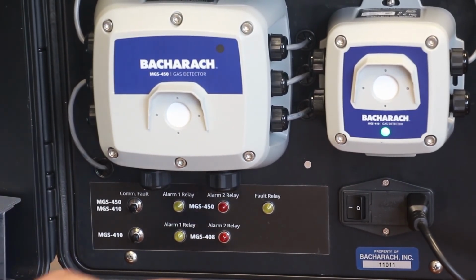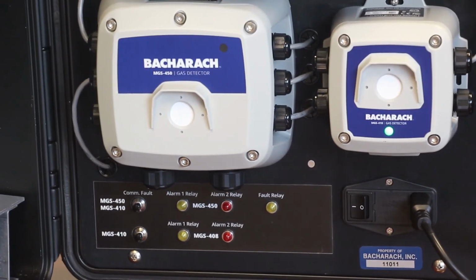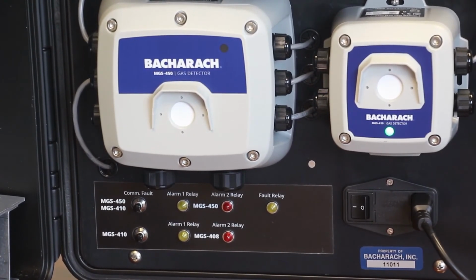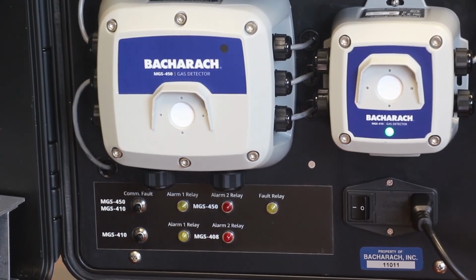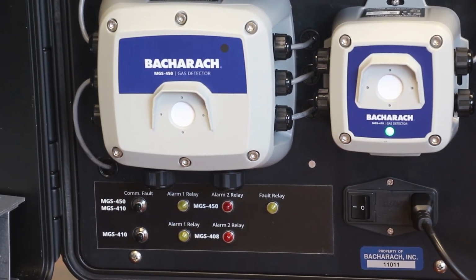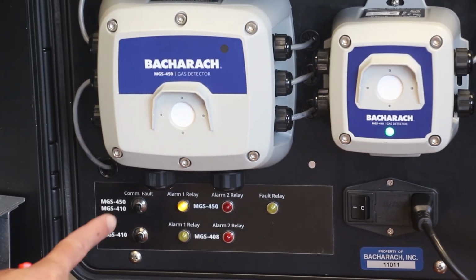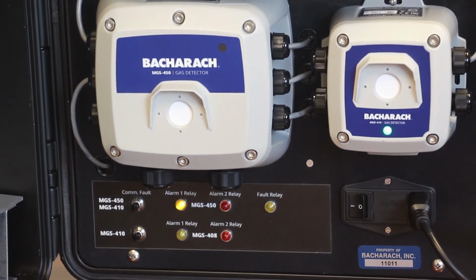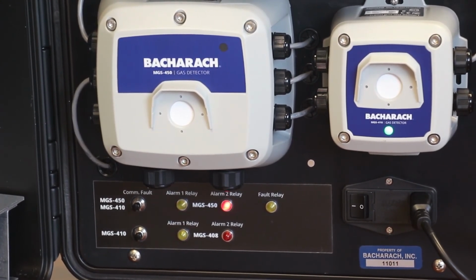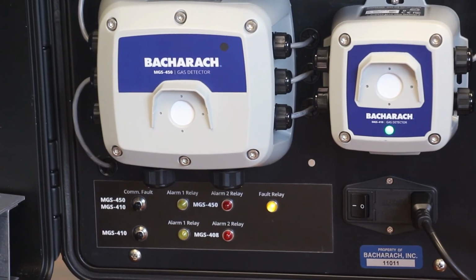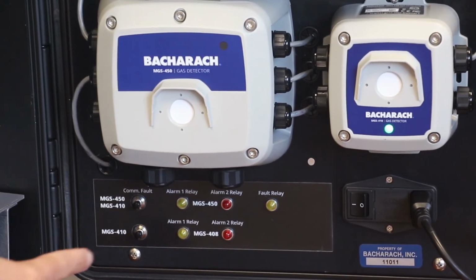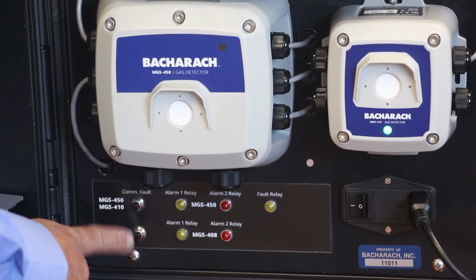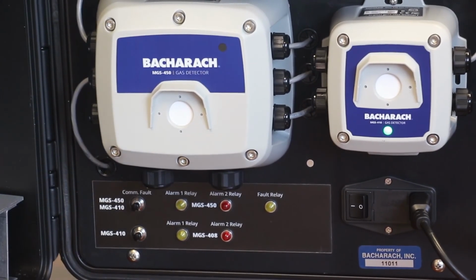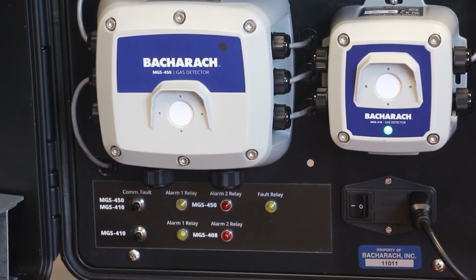And then if we use this small panel down the bottom here, in conjunction with the app, we can highlight and demonstrate relay switching. So if I switch relay 1 here, you can see the small yellow LED alarm 1 relay lights, relay 2 for the alarm 2 relay, and relay 3, which acts as a fault relay. On this small panel at the bottom here, we also have these two buttons for both units. Let me just come back out of the output test enable mode.